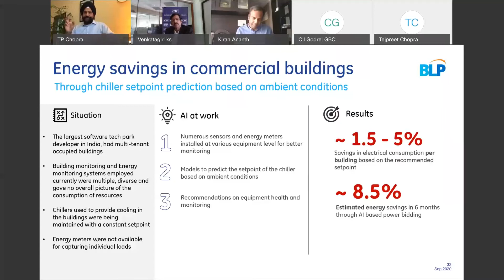As a result of it, just for a very short period of time, just by changing the set points based on these algorithms, we were able to achieve, based on the seasonal impact, anything between 1.5% to 5%, and actually save them over 8% of energy costs in just 6 months. So this is just a quick example of some of the output.